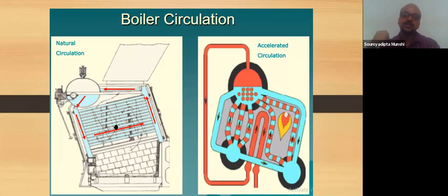As the density of the steam is low, the steam is separated and the existing water mixes with the flow of the water which comes from the economizer, then again goes back to the water tube or through the downcomer, and the cycle is repeated and steam generation is in process. So the circulation in this case takes place, it is called the thermosiphon principle.